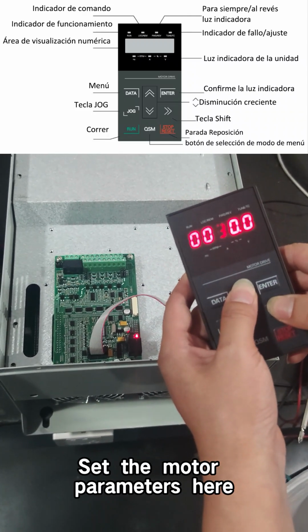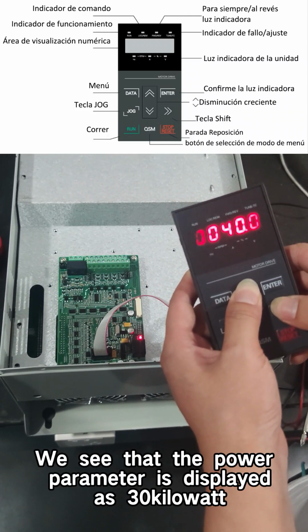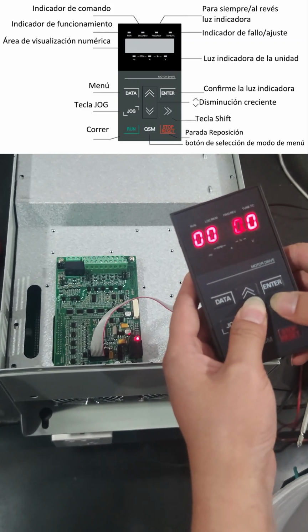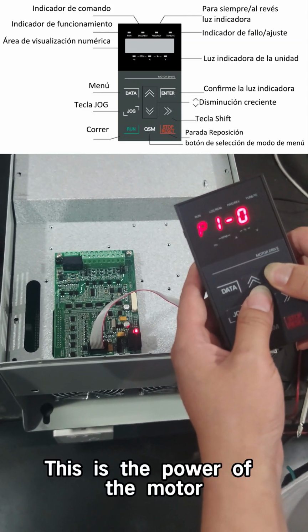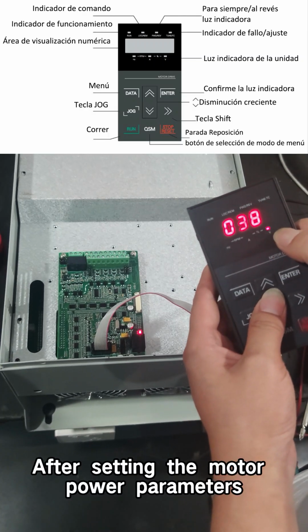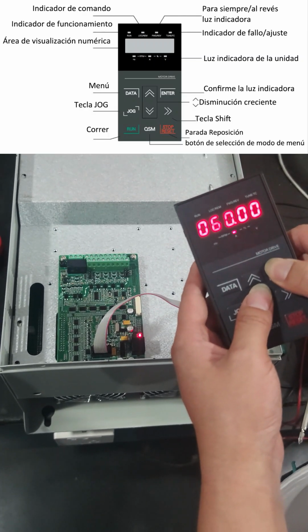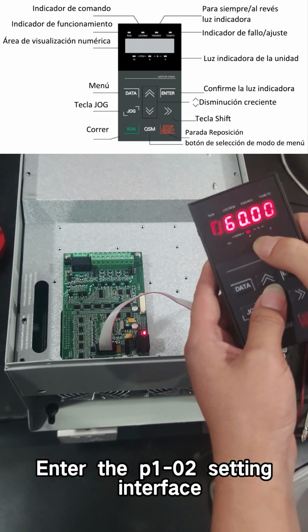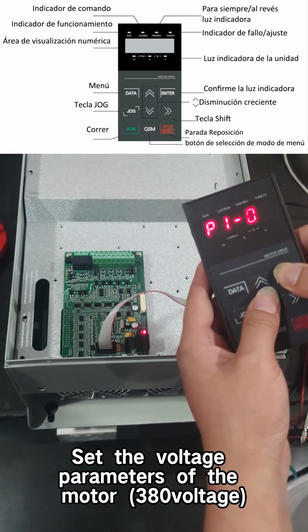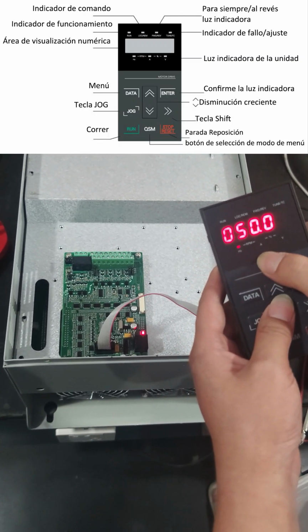Set the motor parameters here. We see that the power parameter is displayed as 30 kilowatt. This is the power of the motor. After setting the motor power parameters, enter the P102 setting interface. Set the voltage parameters of the motor, 380 voltage.